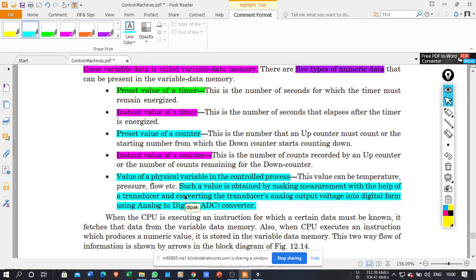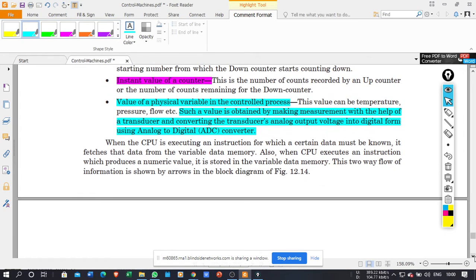So basically a transducer is a device which converts a physical parameter into a voltage or electrical signal. Remember, a transducer converts a physical parameter, temperature, pressure, flow, acceleration, velocity, into an electrical signal. That may be voltage or current. If it is a voltage, it may be 0 to 10 volts or minus 10 to plus 10 volts. If it is a current, it may be 4 milliamperes to 20 milliamperes signals, like that. But as my PLC does not understand the analog signal, I need to convert my analog signal into a digital signal with the help of an ADC.